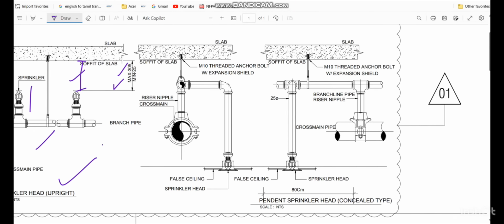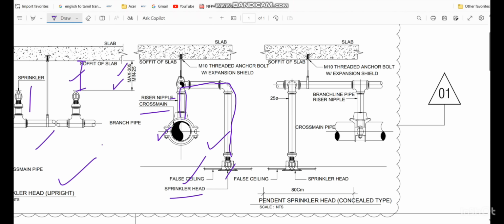Then coming to the second case, one important thing. Like you see here, this is the cross main again, and we have the riser nipple, and in this case I have taken the return bend arrangement like this for the pendant sprinkler. So this is the false ceiling. I have taken the pendant sprinkler. Here the thing is, if you are taking the branch, for example a pendant sprinkler, from the cross main, then we have to take a return bend. But in the second case you can see this is the cross main pipe, and we have the riser nipple, and this is the branch line pipe, as indicated here. So if you are taking the branch from the branch pipe for the pendant sprinkler like this, there is no need to follow the return bend. But if you are taking the pendant sprinkler pipe directly from the cross main pipe like this, then you must provide the return bend like this.